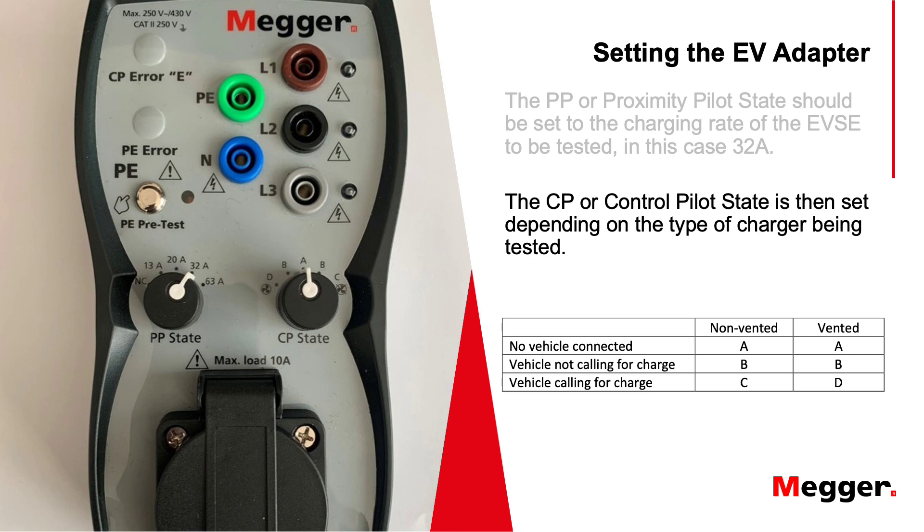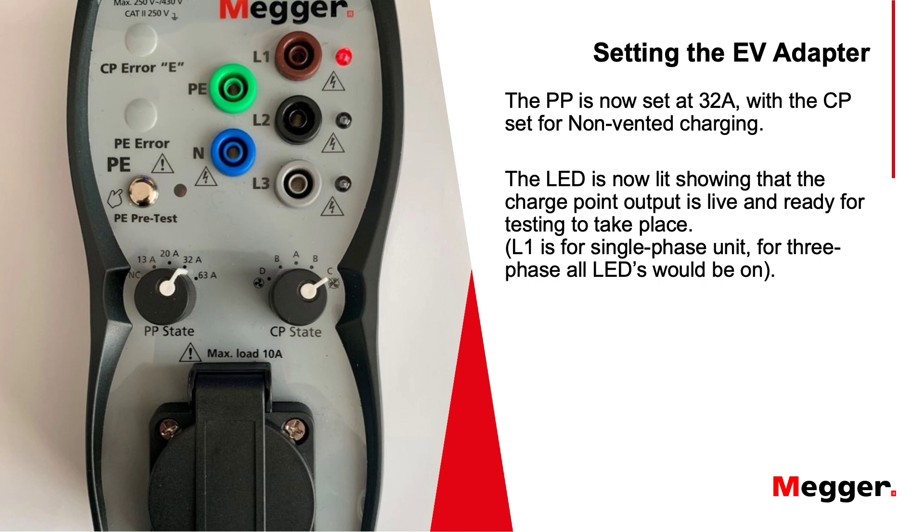In both cases, A is no vehicle connected, B is the vehicle connected but not calling for charge, and C and D represent a vehicle connected when it's calling for charge. Setting it to C will close the contactor within the charge point and liven up the EV adapter. You can see that the phase light next to L1 is lit — this is because it's a single phase version; should it be three phase, all three lights would be illuminated. We're now ready to continue with tests.